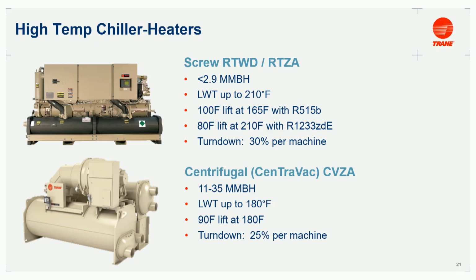If you go to a K-12 school trying to get them to bite on this whole electrified heating thing, you can explain these exotic, brand new machines that make 200 degree heat with a special compressor, or you can just give them another machine that looks exactly like the one they already have in the building. So what we're able to do is produce these hot water temperatures using more traditional HVAC equipment.